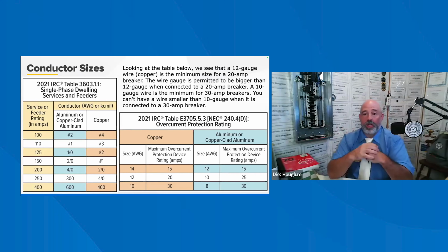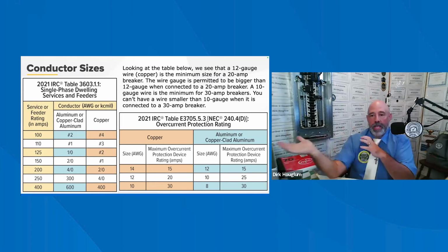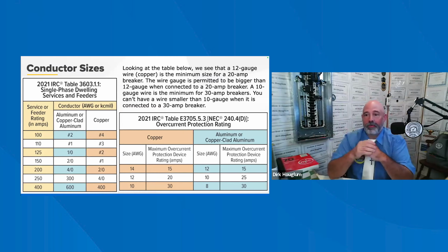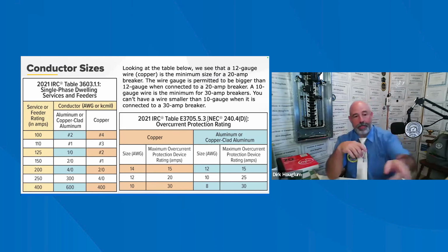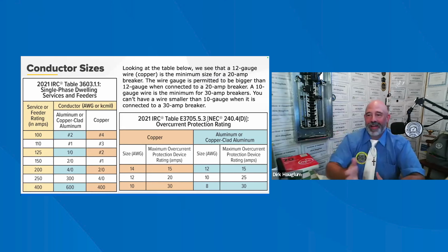for any given amperage. For a commonly installed 200 amp service, the service entrance cable, the SEU, between the meter base and the main electrical service panel with the integrated main disconnect, will have a number 4 or 4-aught aluminum conductor for the hot. Remember, the lower the number, the bigger the wire. Looking at the table, we can see that the 12 gauge copper wire is the size for a 20 amp breaker. If the wire is bigger than 12 gauge, a 10 gauge wire is used instead. So the 10 is for a 30 amp, and so on and so forth.